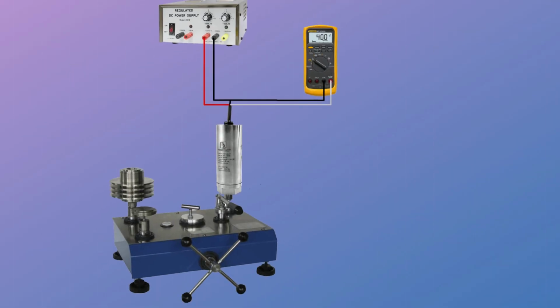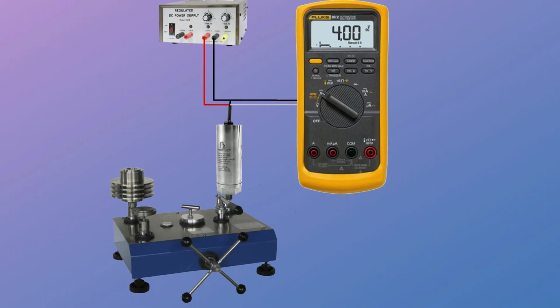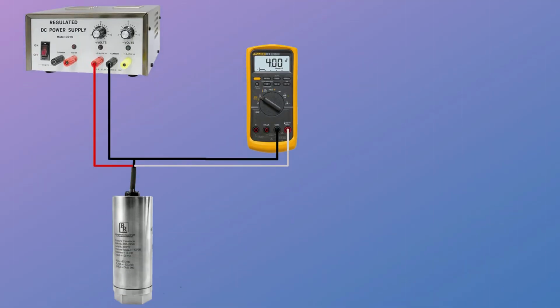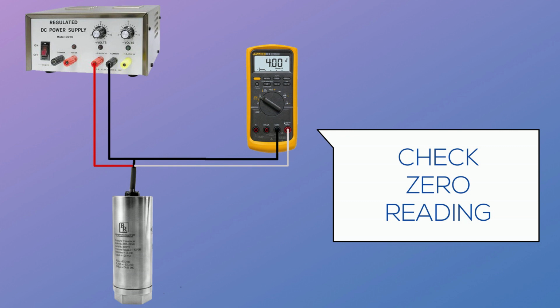If just a 2-point calibration or verification is required, a zero reading is first obtained. Once zero pressure is reached and it's had time to settle, verification of the zero reading can be determined. In this example, that would be 4 milliamps. There will be a factory tolerance on the zero reading called the zero balance. This can be obtained from the product data sheet or directly from the factory.